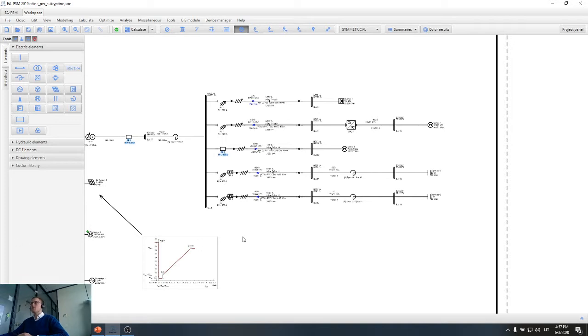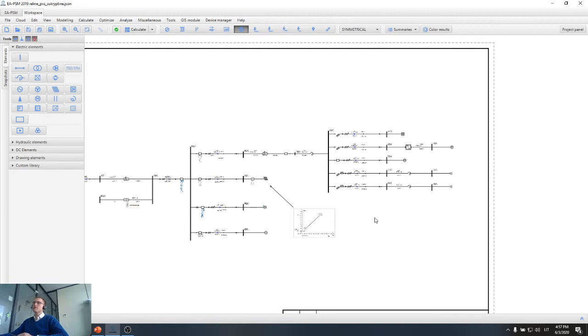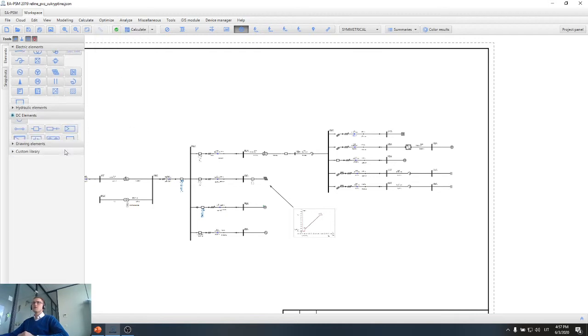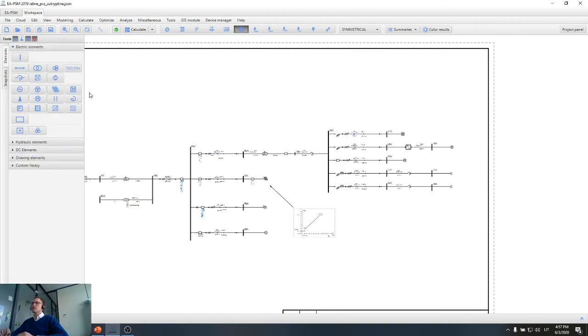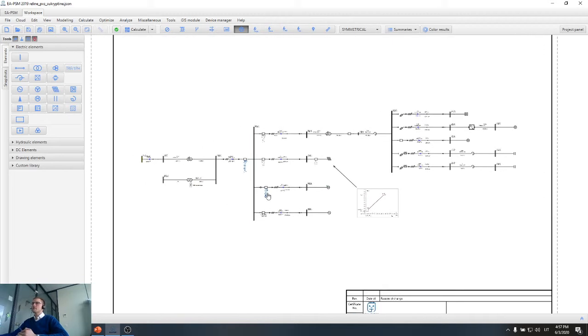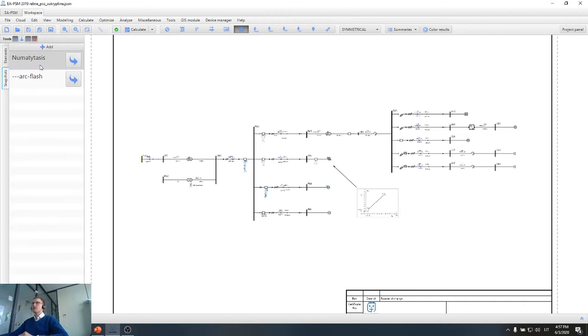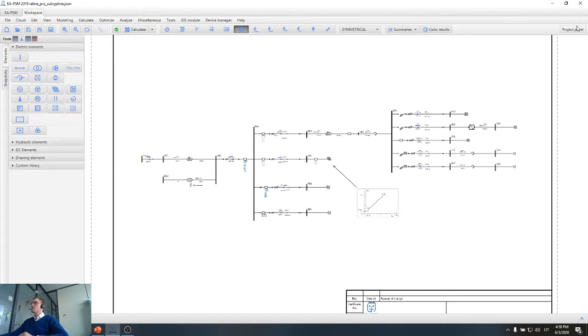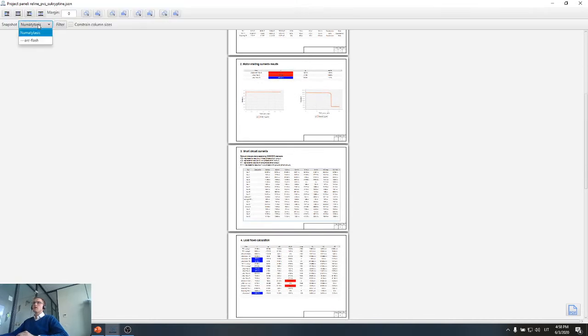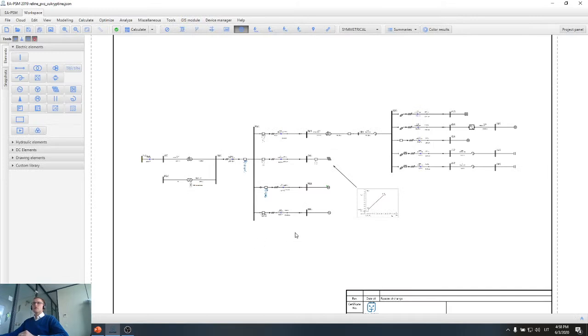As I have mentioned, I showed only part of the functionality. If we look closer, we have transient analysis, solar irradiance modeling, wind turbine power quality, relay coordination, basically automatic functionality for overcurrent relay coordination, protection tracking, insulation coordination, DC battery sizing, cable sizing, also DC network design. So there are many functionalities. Also, if we need to analyze different states of the network, we have snapshot systems where we can create different scenarios, and later when we make a report, we select which calculated scenario to use, so we can represent results from any of the scenarios analyzed. This allows creating a comprehensive report about the network.